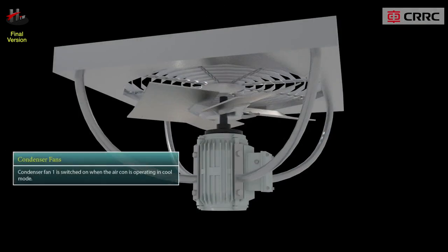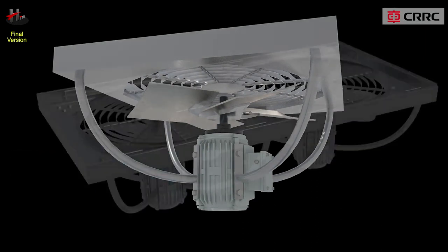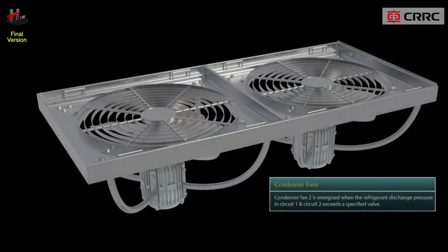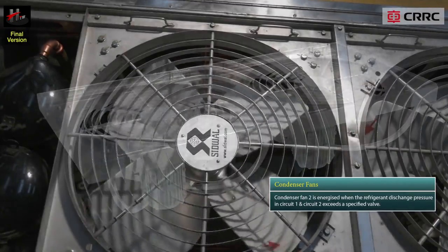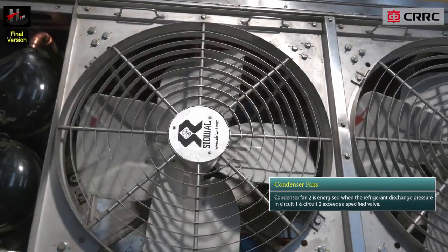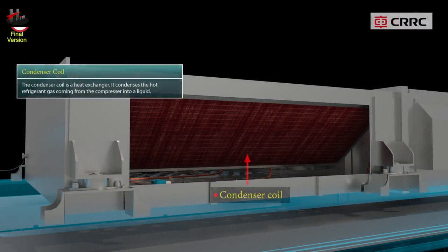Condenser fan 1 is switched on when the air conditioner is operating in cool mode. Condenser fan 2 is energized when the refrigerant discharge pressure in circuit 1 and circuit 2 exceeds a specified value. The condenser coil is a heat exchanger.